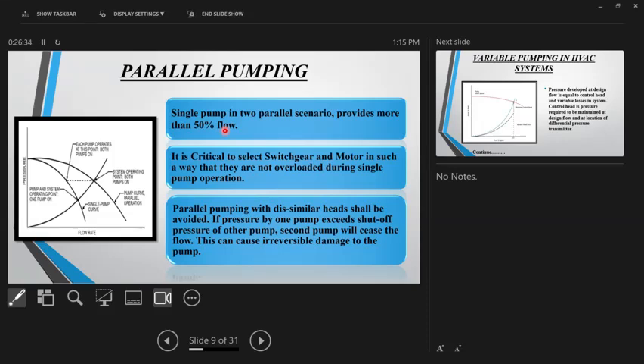Why is it a problem? Usually, the power requirement of the pump is proportional to flow as well as pressure. But the reliance on head is less compared to flow when it comes to power. So when one pump starts over-pumping, there is every possibility that it will consume much more power, in which case you may overload your starters. This is just an example to tell you. This hardly happens when there are two or three pumps, but it can definitely happen when there are multiple pumps, like 10, 15, 30, which happens in the case of data centers.